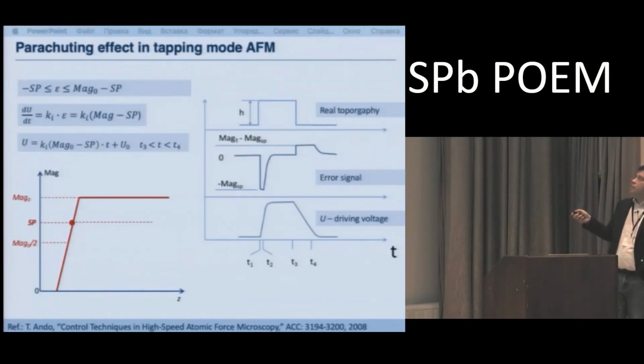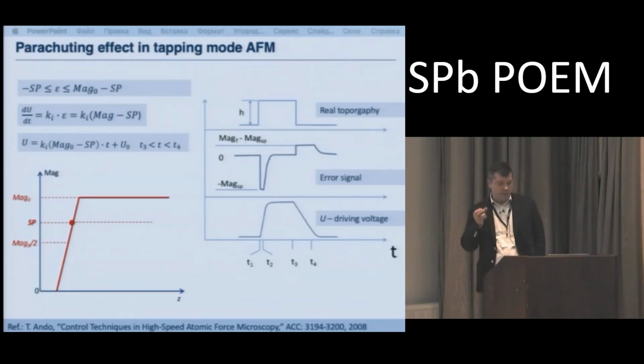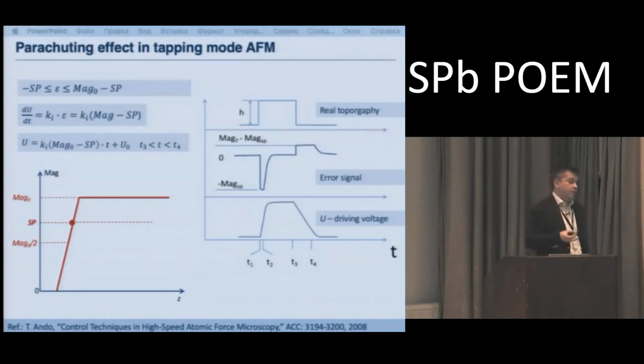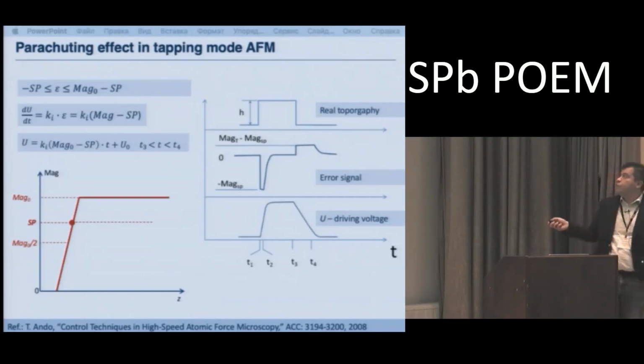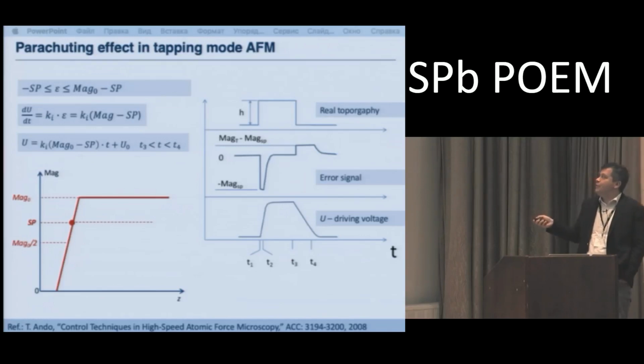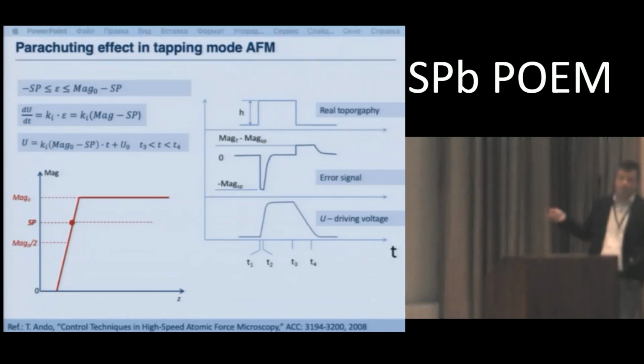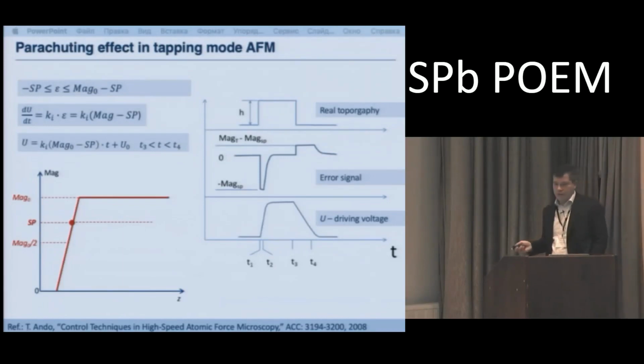So once we go to the step, the amplitude of the cantilever oscillation drops to 0 quite fast, within the time scale of the time constant of the cantilever itself. As a result, we have a constant signal on the input of the feedback system, and then a linear dependence on the measured topography. When we jump down from the step, we again have the linear dependence on the topography.